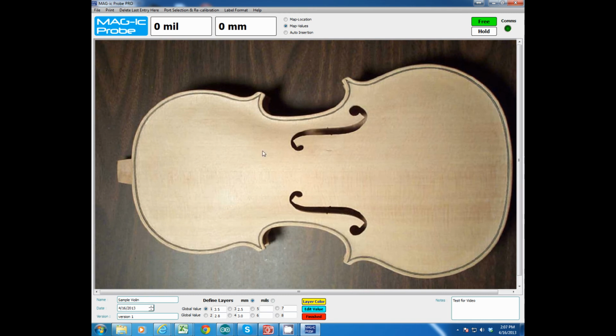This should be the same as what you've defined to do your measurements on the instruments, which you'll remember is in millimeters. And you're going to define layers, anything up to 8 different layers. Now these have nothing to do with your actual plate itself that you've measured. So in this case we measured the top plate of the instrument. So these layers have nothing to do with that top plate except to define the outline. So layer 1 will always be the actual outline of the instrument.